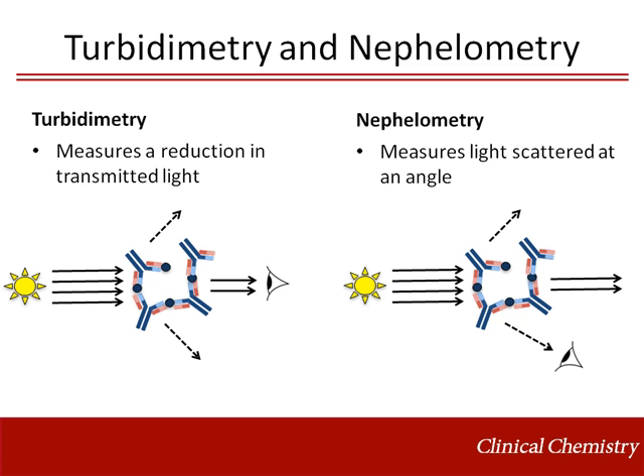Aggregation of antibody and antigen into large complexes is another common method used in clinical immunoassays. Both turbidimetry and nephelometry are based on the concept of light scattering. Turbidimetry measures a reduction in light transmission as a result of antigen-antibody complex formation; as complexes form, light scattering increases while light transmission decreases. Conversely, nephelometry detects a portion of the light that is scattered at a chosen measurement angle by the antigen-antibody complex; as complexes form, light scattering at the measured angle increases.